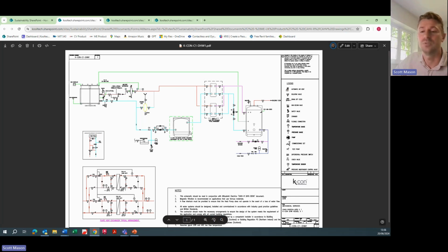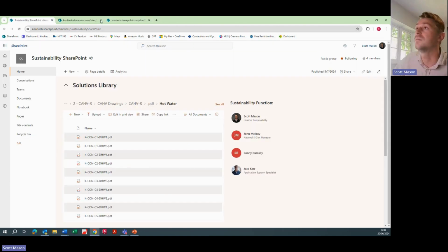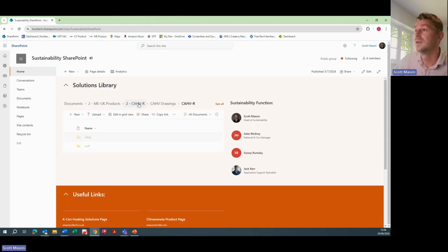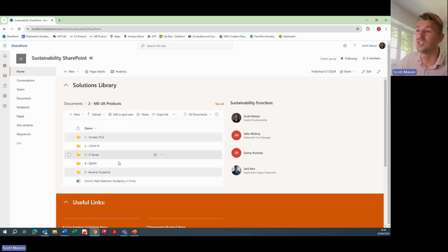That means the primary loop's not going to drop in temperature sharply. And if it's not going to drop in temperature sharply, you've gotten rid of that risk of the defrost process, unless for some reason you've got a hot tap which is permanently open, stripping out and exceeding everything this unit is capable of delivering. But that would be a very specific process, in which case it's a site-specific thing, and we'd be looking at a totally different style of application. So you would get your schematic, and what you'd also get, of course, is your suite of complementary materials that are going to work with that.